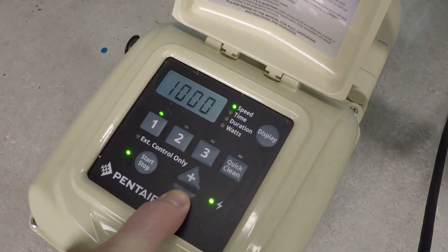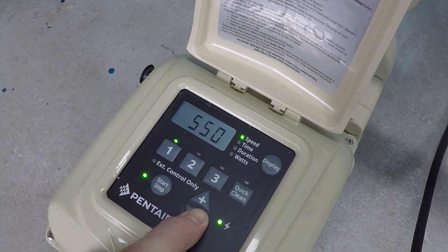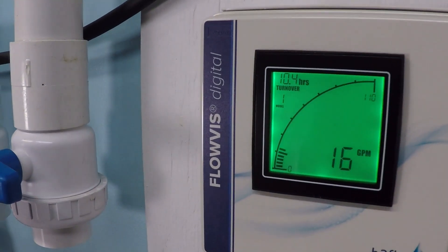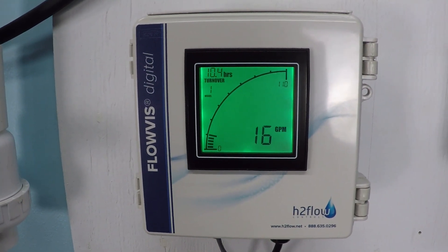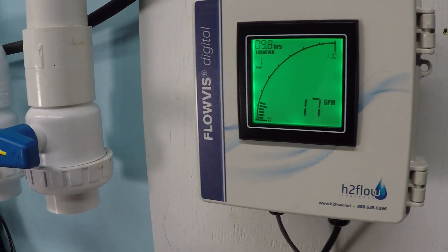Now we're dropping all the way down to 550 rpm. As noted, not every pool would even move water at this speed, but in this example we can. The flow meter reads 16 to 17 gallons per minute, and the power consumption is a scant 62 watts — very little power for a surprising amount of flow.